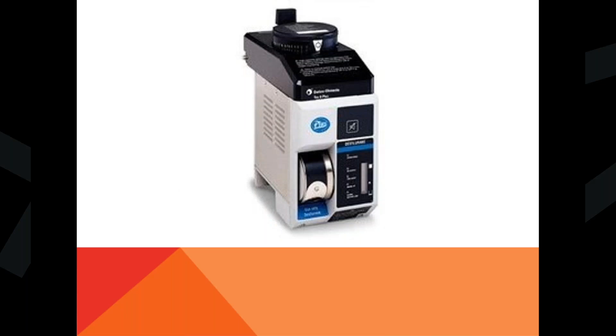And then here's a Datex-Ohmeda, and I think Baxter still makes these, the Tec 6. It's got a little different setup as far as the fill. It's got a different kind of bottle and adapter. The agent bottle actually has a key on it, so you can't mix ISO with Sevo or desflurane. They are keyed to prevent you from putting the wrong gas in the wrong vaporizer, which would not be a good thing.